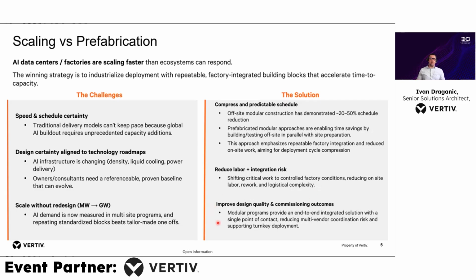The quality of design is much better too. When something is built at the factory, it's on the floor level, built with precision and skilled workers, compared to site work which is always on ladders, somewhere high above near the ceiling where the bus bars go, with somebody trying to install a tap-off box. The quality of the build is just better when we do it in the factory, and the commissioning outcomes are better too, since these things are pre-commissioned and tested before they come to site.